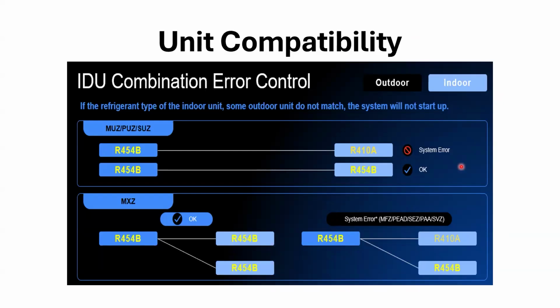And the other part of it is putting R410 and R454 equipment together. That's been happening, so FYI. It doesn't run good. Operational problems, running hot. So again, that's MUZ, PUZ, SUZ, one-to-one scenario, and then here's your smart multi-units right here. So again, just showing you, they're not compatible with the other refrigerant.